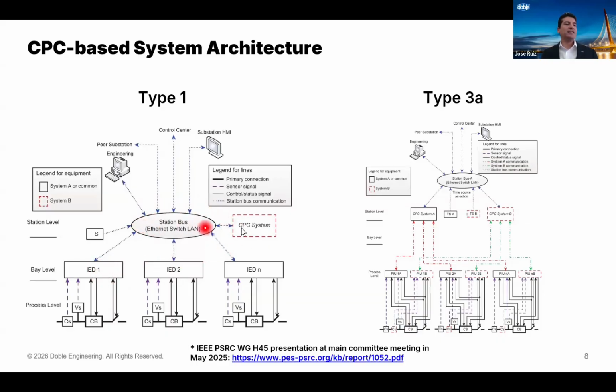But notice that the centralized device is used as a backup, because we have the microprocessor-based relays getting the data from the instrument transformers in an analog format, but the same microprocessor-based relays are basically digitalizing the signal and making that available for the backup CPC system. So we can see multiple microprocessor-based relays and one backup system, a centralized protection.